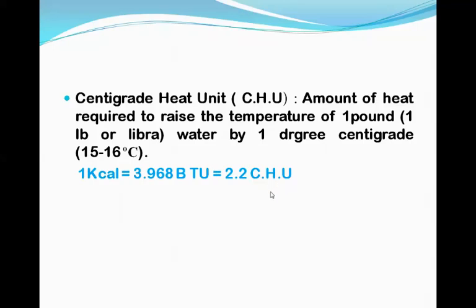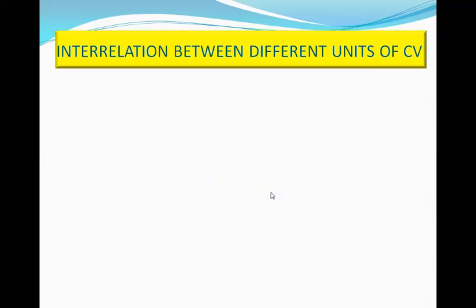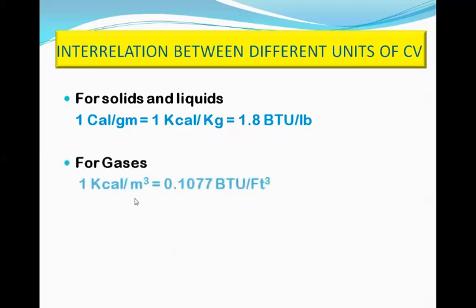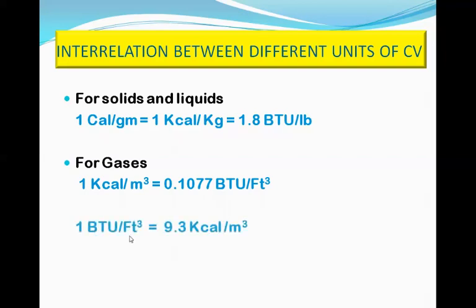The heat given per unit volume or per unit mass is known as calorific value, and there exists a relationship between the different units of calorific value. For solids and liquids, since calorific value is expressed per unit mass: 1 calorie/gram = 1 kilocalorie/kg = 1.8 BTU/lb. For gaseous fuels, since it is per unit volume: 1 kilocalorie/m³ = 0.1077 BTU/cubic feet, and 1 BTU/cubic feet = 9.3 kilocalorie/m³.